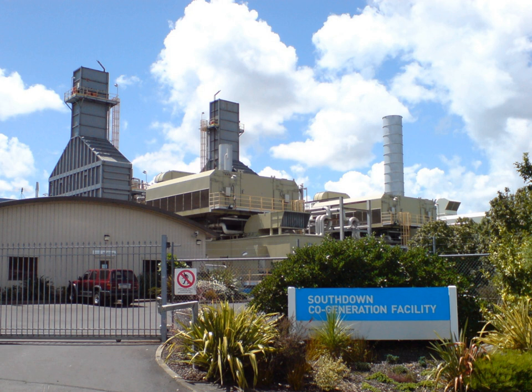Gas turbines designed with foil bearings and air cooling operate without lubricating oil or coolants. The waste heat of gas turbines is mostly in the exhaust, whereas the waste heat of reciprocating internal combustion engines is split between the exhaust and cooling system. External combustion engines can run on any high temperature heat source; these include the Stirling engine, hot air engine, and the steam engine, both ranging from 10% to 20% efficiency. Other possibilities include the organic Rankine cycle, which operates at lower temperatures and pressures using low-grade heat sources. The primary advantage is that the equipment is essentially an air conditioning or refrigeration unit operating as an engine, whereby the piping and other components need not be designed for extreme temperatures and pressures, reducing cost and complexity.